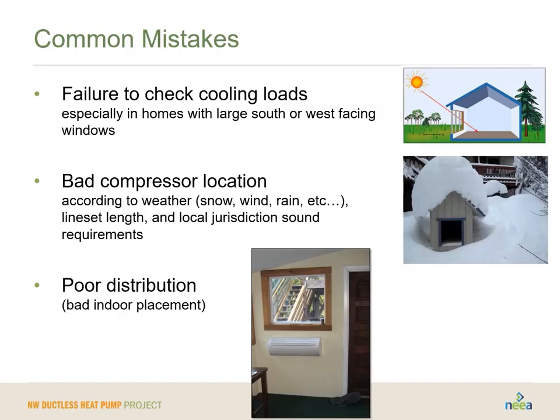So one thing you can do, particularly if you notice a house with a lot of large south and west windows, is upgrade your way of thinking to using an engineering sizing tool, to make sure that you're going to size your system to actually meet both the heating and cooling loads of the main body. The second is bad compressor location, right?